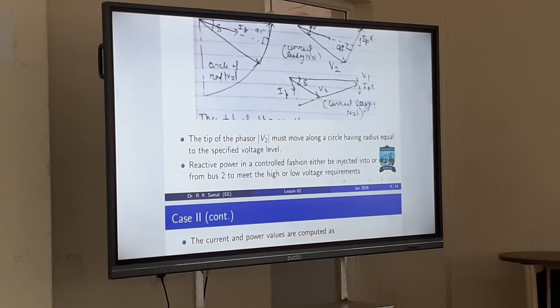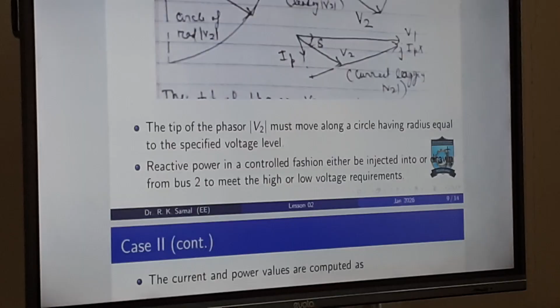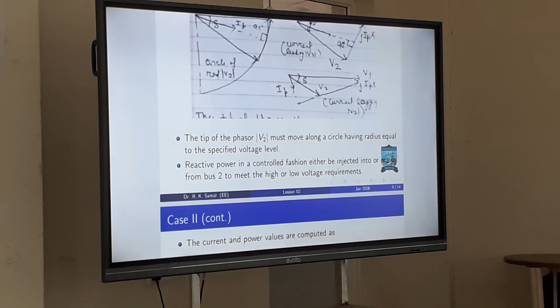See, whenever you allow the voltage to vary, you are not bothered about the reactive power. But if you want to keep the voltage constant, reactive power must be supplied. So just like wind farms. Suppose a wind farm is connected there as part of a distribution system. You know that wind farms use induction generators. They have no source of reactive power, so they take reactive power from the grid itself. So that will reduce the voltage. Therefore, we need some reactive support for the induction generators. Similarly, to maintain the voltage, we need reactive power support.